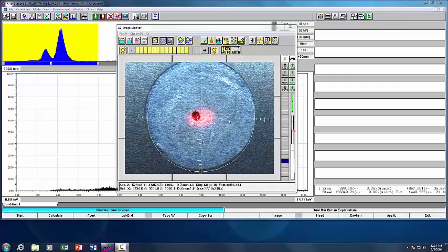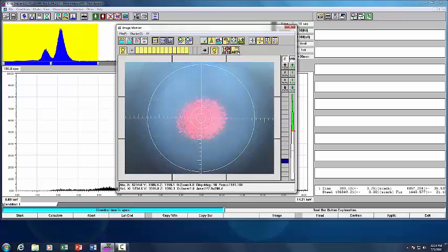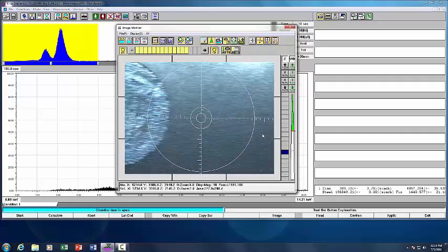The camera moves into focus, but our head did not move, just the camera. I want to move the X-ray tube head so it's at the same height as the last measurement, so I will hit auto approach. The head moves and automatically focuses. I'll now move back to the lower one and show you reverse.